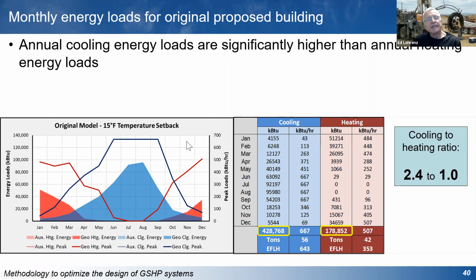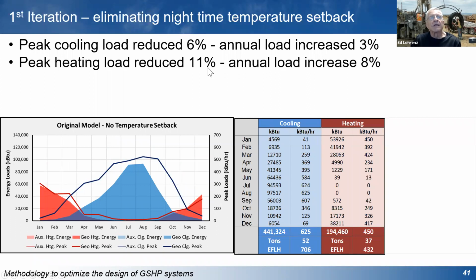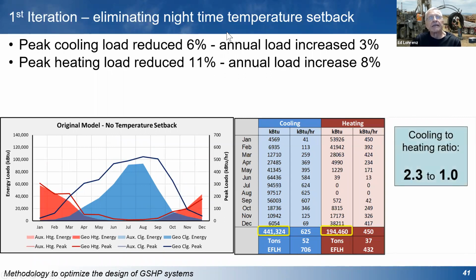Note that there's a 15-degree temperature setback on the operation of the building built into the energy model of the building. So that really has an influence on what the peak loads are. That number is actually fairly close to the rules of thumb, 400 square feet per ton. If we simply eliminate the nighttime temperature setback in heating and cooling, that reduces the peak loads by about 6% in cooling and about 11% in heating. It increases the annual cooling load slightly, about 3%, and the annual heating load by about 8%. It's reduced this ratio from 2.4 to 2.3 to 1. So this has been a little bit reduced. This has increased a bit.